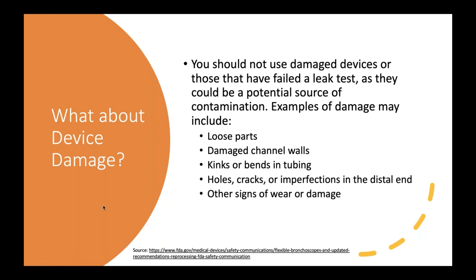When medical device outbreaks are investigated and devices torn apart by factory technicians, they can pretty quickly determine there are many broken pieces — things not properly maintained, seals and O-rings not properly seated. If you ever have a device that's visibly damaged or fails a leak test, we shouldn't be using it. We need to follow the manufacturer's instructions, remove that device from service, and get it serviced appropriately. Look for things falling out of the device, kinks or bends, holes or cracks, or other wear and tear. Some people use a borescope — but I equate that to reading a chest X-ray if you've never learned basic radiological imaging. If you don't know what you're looking at, it's very difficult to interpret the image.